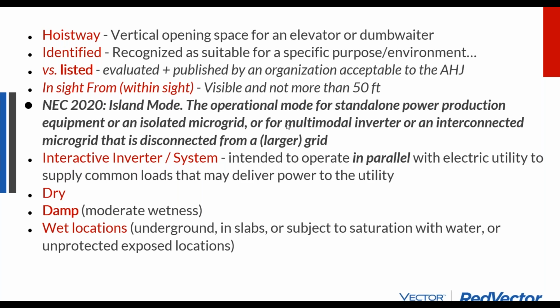The grid in this case is playing jump rope, and your inverter has to jump in and synchronize to the grid. So parallel inverters have to be synchronous, they have to mimic the grid, and they can't generate their own grid form. And so that gets into the bidirectionality of charging in parallel or not in parallel and out of sync. All of these terms are precisely referred to in the National Electric Code. A damp location is moderate wetness. Wet locations can apply to slabs.